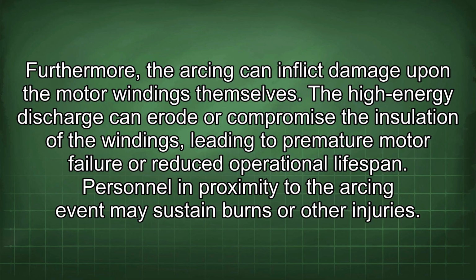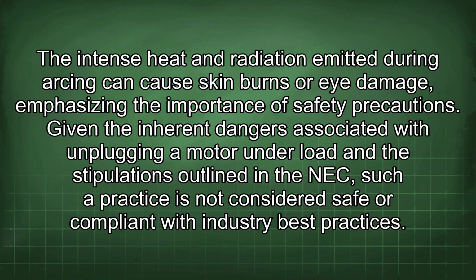The high-energy discharge can erode or compromise the insulation of the windings, leading to premature motor failure or reduced operational lifespan. Personnel in proximity to the arcing event may sustain burns or other injuries. The intense heat and radiation emitted during arcing can cause skin burns or eye damage, emphasizing the importance of safety precautions. Given the inherent dangers associated with unplugging a motor under load and the stipulations outlined in the NEC, such a practice is not considered safe or compliant with industry best practices.